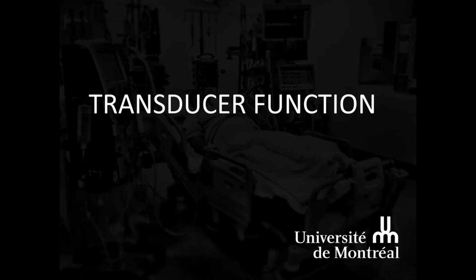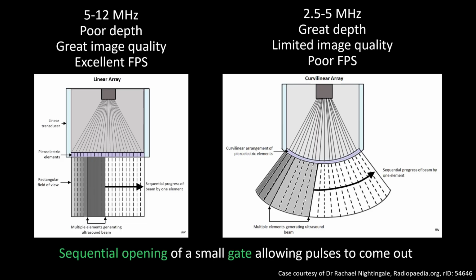We'll talk about transducer function, as it has a major impact on image generation, mainly because of the different ways ultrasounds are produced. We'll not go into impressive detail, but rather focus on the differences between the transducers. Linear array and curvilinear array are specific methods of generating ultrasound beams. They function by having a sequential opening of a small gate to allow pulses to come out. The same gate stays open during listening. This, in essence, limits the amount of noise coming from structures outside the beam. Once a beam is done, the next gate opens, and so on.